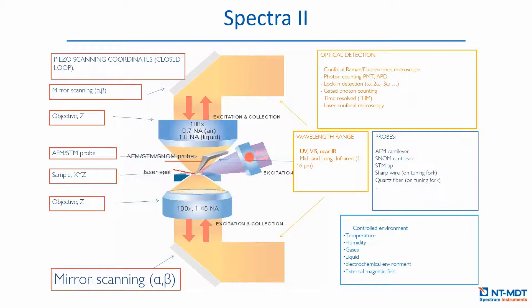Another additional optical access is side illumination. This is not a common configuration because when you do side illumination, the confocal Raman becomes somewhat non-confocal — the shape of the laser spot becomes more elliptical rather than circular, which raises questions about the data obtained.